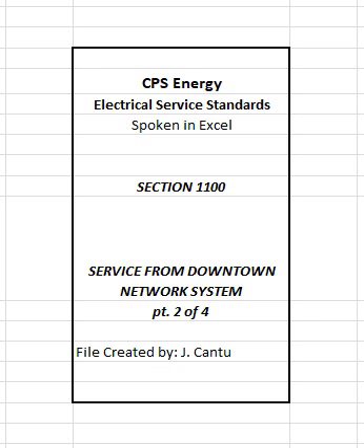G. Ventilation. Fan-forced natural air cross ventilation shall be provided. 1. The transformer vault or room shall be vented directly to an outdoor area. The transformer vault or room ventilation shall not be mixed with the building ventilation or cooling system. 2. Ventilation consisting of 2 each 24-inch diameter ventilators must be provided. Lower ventilator shall be 12 inches above floor. Upper ventilator shall exhaust to outside air and be 12 inches below ceiling or as otherwise approved by CPS Energy.